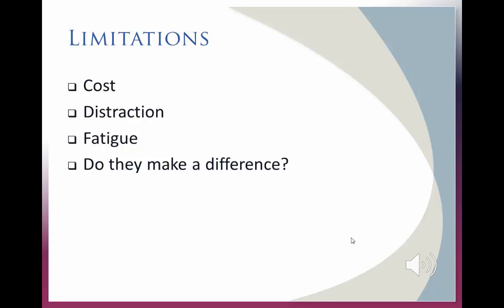The haptic devices with 6 degrees of freedom and 3 degrees of force feedback are significantly more expensive than those with fewer degrees of freedom and 1 or no degrees of force feedback. In some cases, haptic devices may become a distraction for the trainee, especially if there is significant friction or vibration within the device. This may also lead to fatigue as the trainee tries to balance task completion with the need to suppress or ignore the odd haptic sensations.